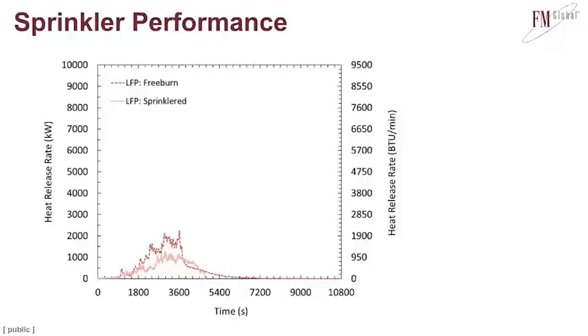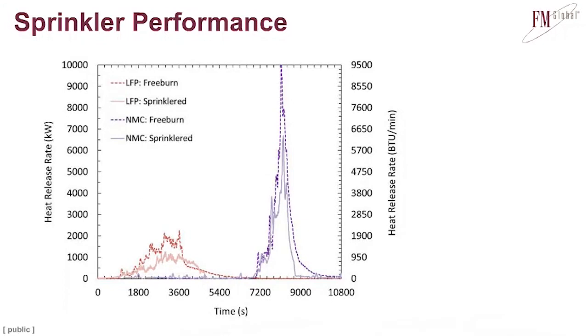If you look at the dashed orange line, that's the free burn data. And if you look at the solid line, that's the sprinkler test data. So there actually is a reduction in the peak heat release rate during the sprinkler test. Now, if you compare that to the NMC system, you can see that these two systems represent very distinct hazards. I aligned these data just to separate everything for easy comparison, but you can see that the NMC data peaks at about 10 megawatts, whereas we're somewhere in the range of 2,000, 2,500 for the iron phosphate system. So these are different hazards.